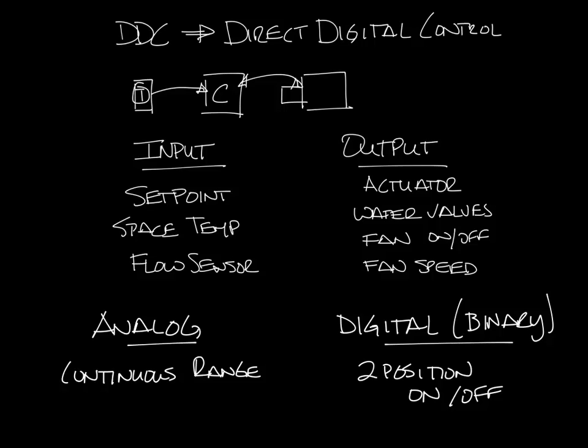Looking at our inputs and outputs, the set point and space temperature would be analog inputs to the controller because they could be any temperature. The pressure signal from the box's flow sensor could be any pressure, so it would also be an analog input. The signal to the actuator and water valves would be analog outputs because they could be a wide range of positions. Turning the fan on and off would be a digital output, but modulating the fan would probably be an analog output.